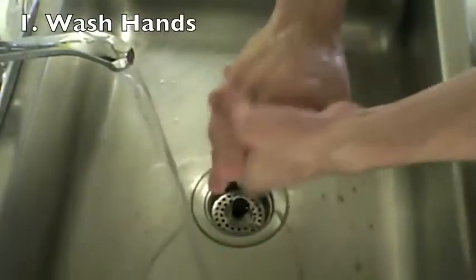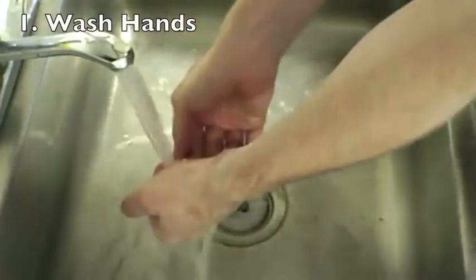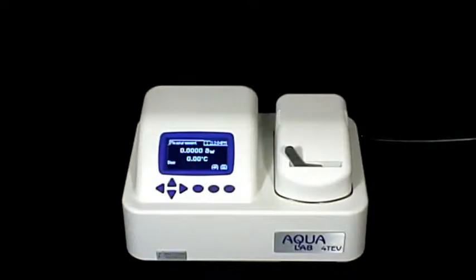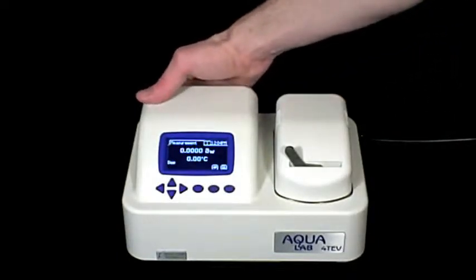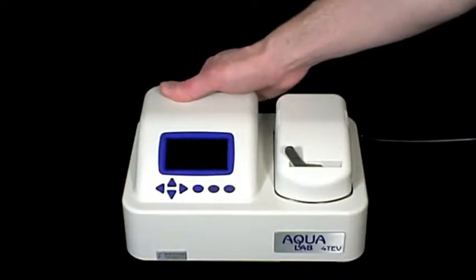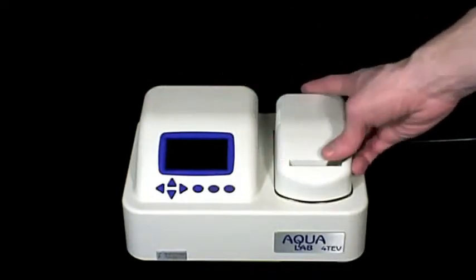Let's get started by washing our hands first. This ensures that oils that naturally occur on the hands do not interfere with the cleaning process. Once you've washed your hands, turn off the power to your Aqualab, and then open the lid to the sensor chamber.